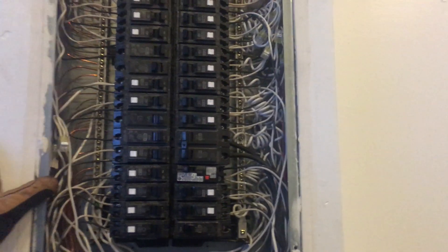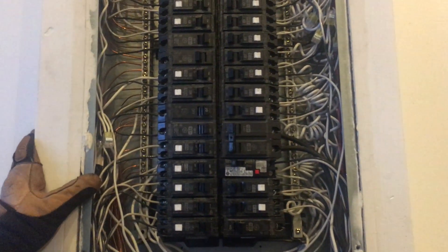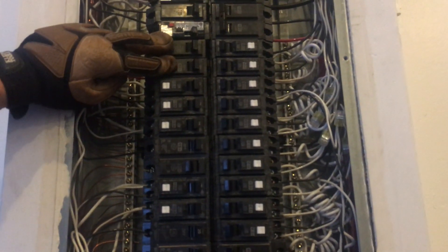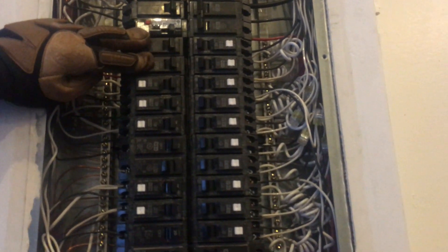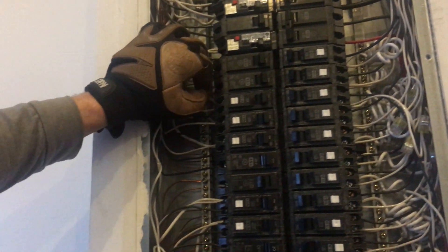You do not want to double up on GFCI protection. This house is about 16 years old, so it already has GFCI receptacles in the proper locations. Keep in mind that when we update, we're supposed to have a GFCI-AFCI dual function for the dishwasher and disposal because it's within six feet of the edge of the sink per Article 210.8. But I'm not sure if they make a dual function multi-sharing neutral yet — I'll find out from GE and call that wholesaler.